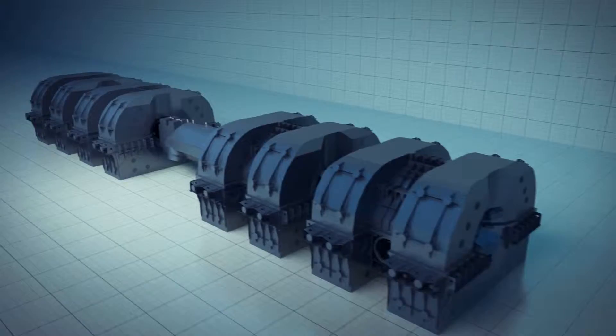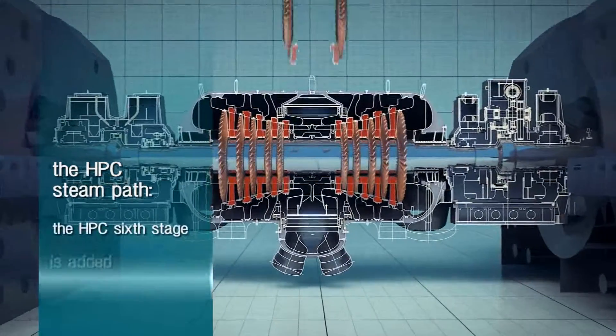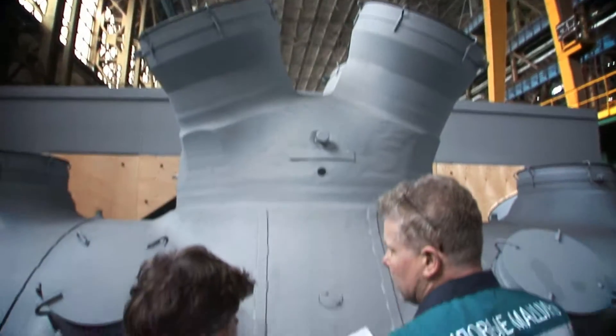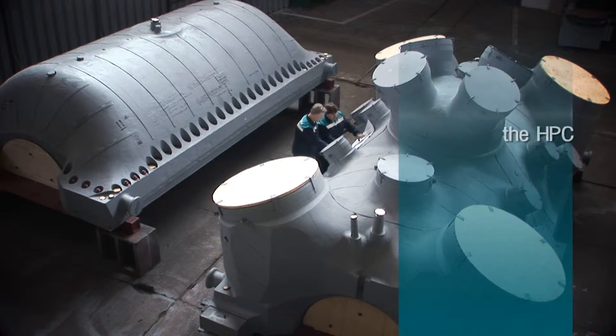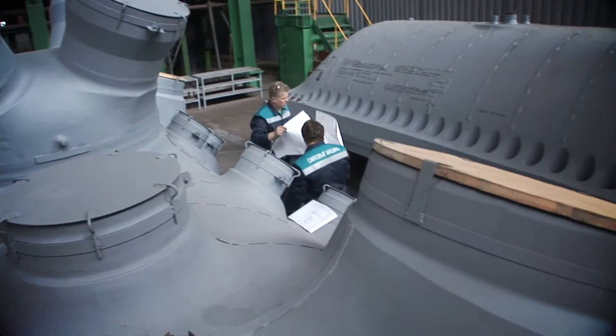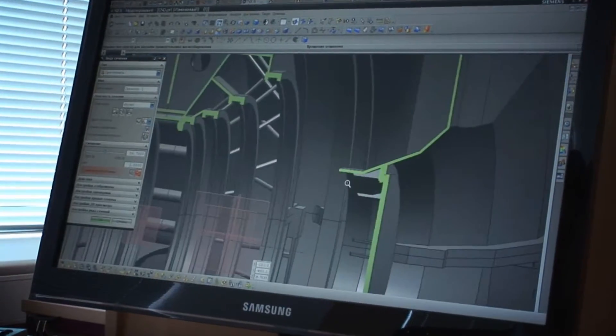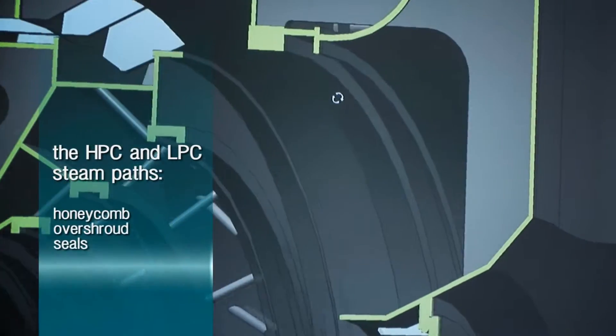The optimum variant for this turbine — a double flow design of the high pressure cylinder with six high efficiency stages in each flow — was designed and implemented. Use of high quality stainless steel for stationary parts of the high pressure cylinder allows the prevention of wet steam having negative impact on critical turbine components. Honeycomb over-shroud seals were used in the high and low pressure cylinder steam paths, minimizing steam leakage and increasing efficiency.